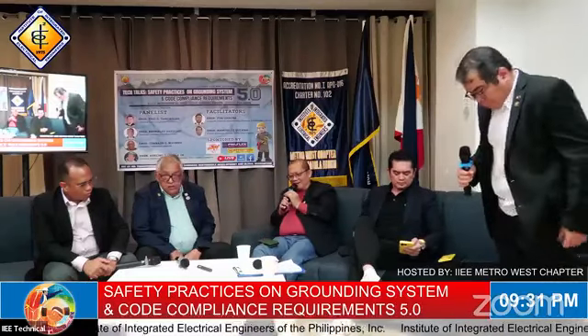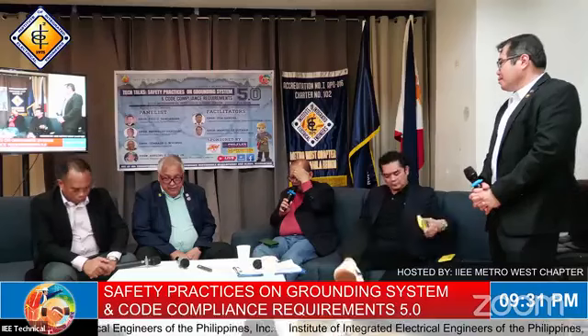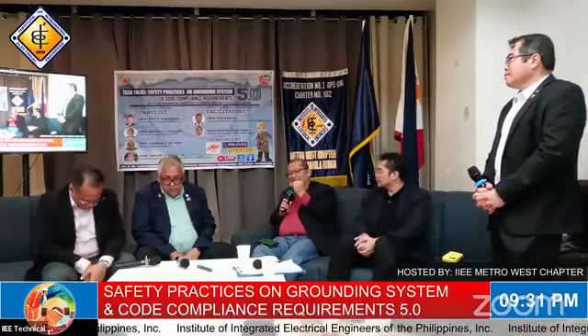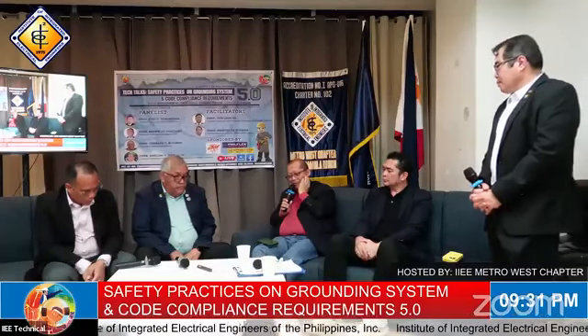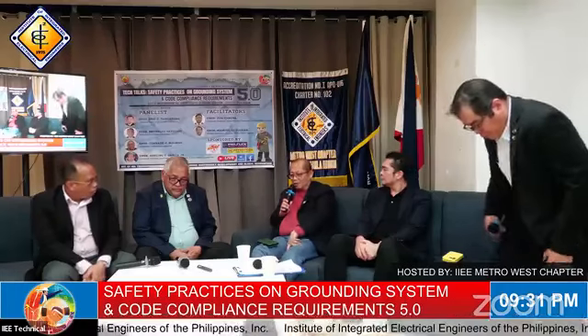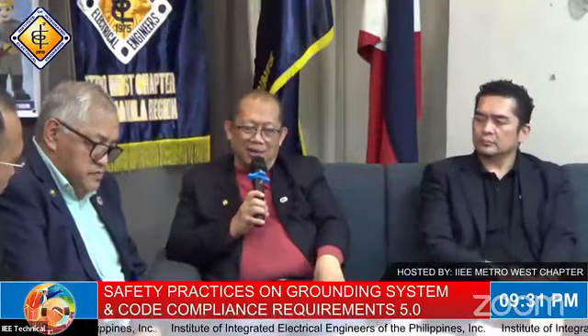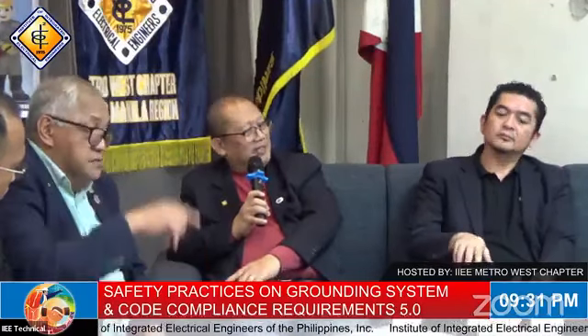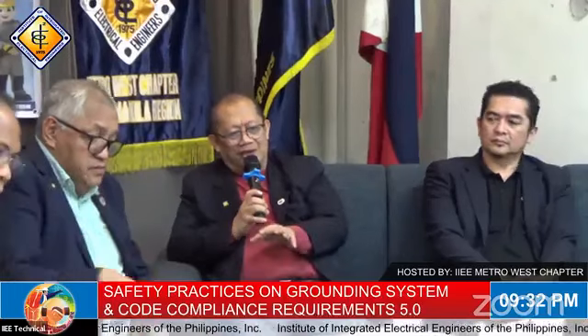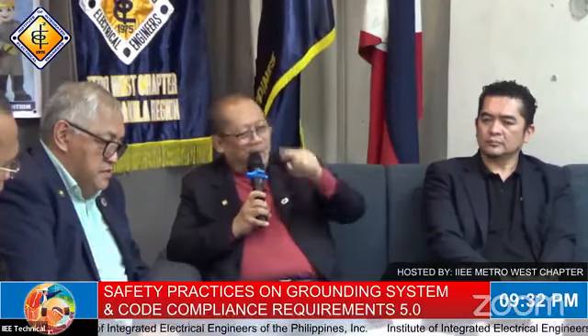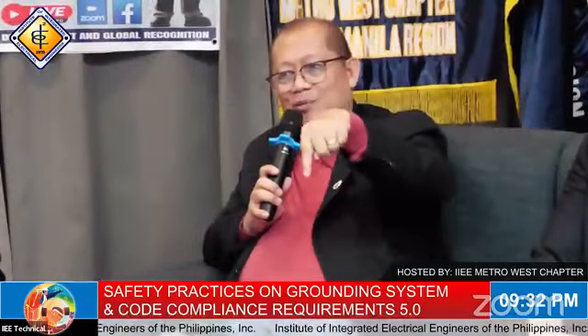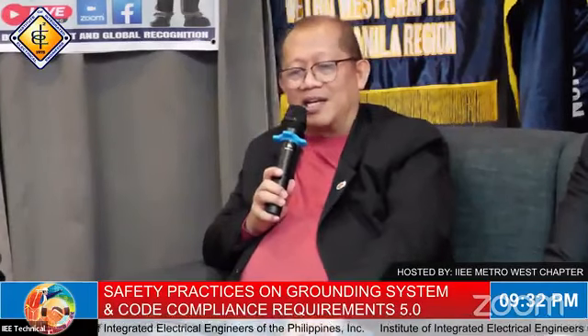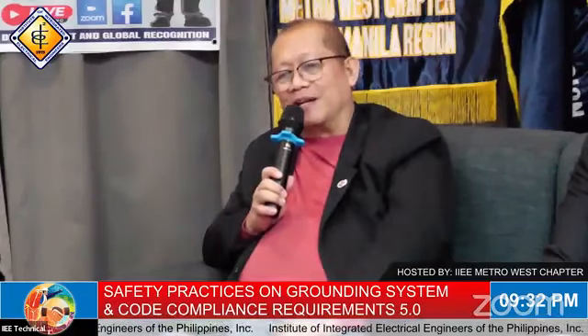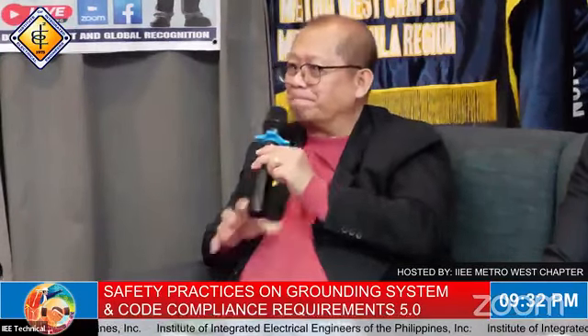Sir Adel: Sige, I'll take a stab at the question. Normally, for a substation or control building within the same area, the presumption is you have an earthing mat or earthing mesh around the whole area, so you should already be covered there. What you may have heard about earthing the foundation bars is normally an issue for high-rise buildings, because sometimes the substation or electrical room area is on the 3rd or 4th level, not at ground level. So that's normally where they tap the earthing from the rebars, so that somehow the dissipation goes down to the ground. But for substations, I don't think it's necessary since the earthing is already there — the earthing mat is more mandatory there and in the control room area. Okay, thanks Sir Adel.